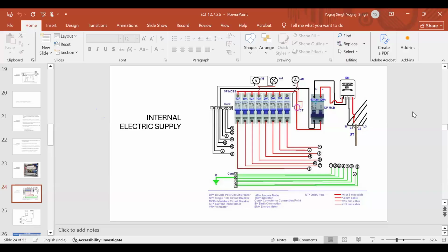Now there is a limitation on how many wires are allowed to pass through the same conduit. The same conduit should not carry wires meant for different phases. This is very clear. Color coding, I will show you a sketch. Color coding is important because one house has been provided with the red phase, the next house will be the Y phase. This has to be done for equalization of load.